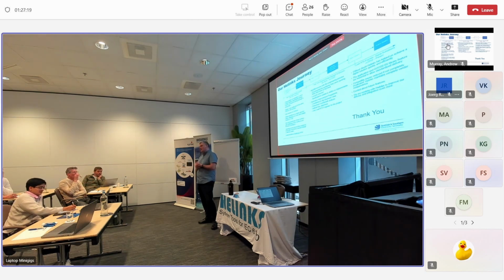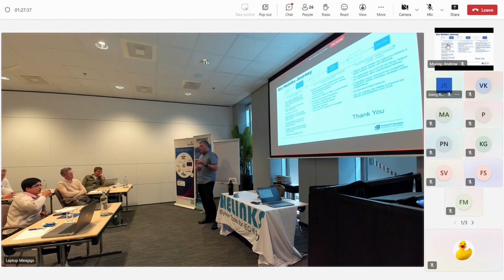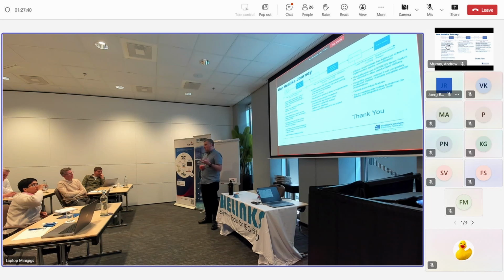No, definitely we should have done a pilot. I joined while those designs were already underway - it's difficult to find the person within SSE who thought that was a good idea at the time, but it was a new technology, a move away from DNP3 protocol, which was our standard. At the time we very much lived in a serial world, so RS-232 connections, DNP3. The step alone from that to Ethernet was big, but the change of protocol as well was too much for everyone to undertake, including the field teams when it came to commissioning.